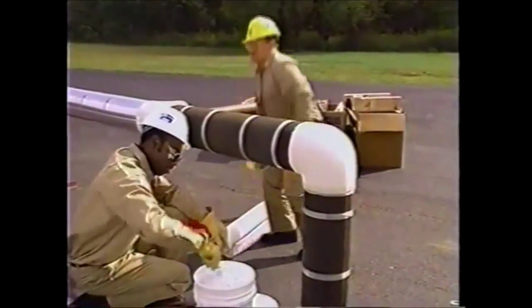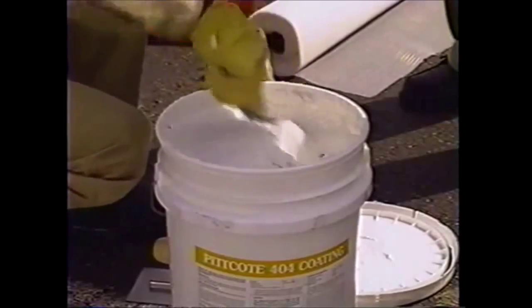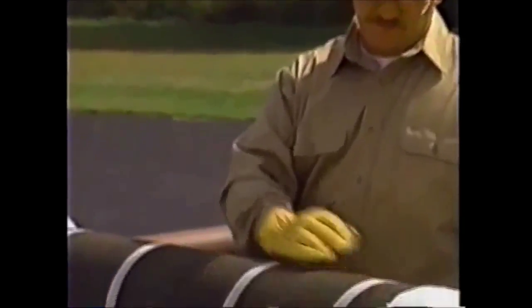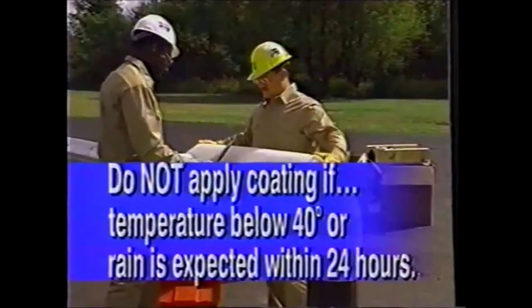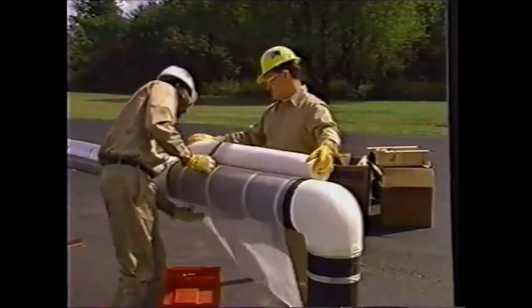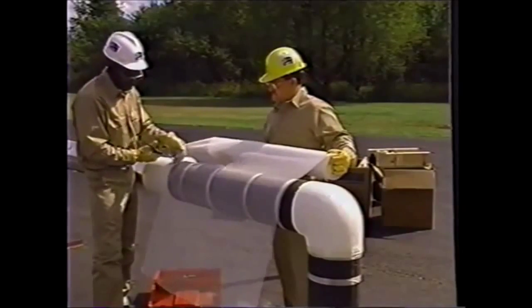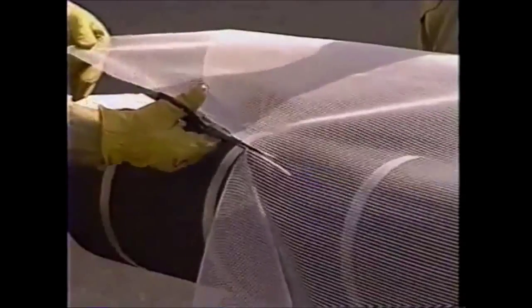In this segment, we'll demonstrate how to apply a mastic finish using Pittcote 404 Coating. To apply the mastic finish, the surface must be free of dust, moisture, and other contaminants. Do not apply the coating if the temperature is below 40 degrees Fahrenheit or if rain is expected within 24 hours. First, cut the PC Fabric 79 into workable pieces to fit the pipe. The fabric must be two to three inches longer than the outside circumference of the insulation. You'll use these after applying the mastic.